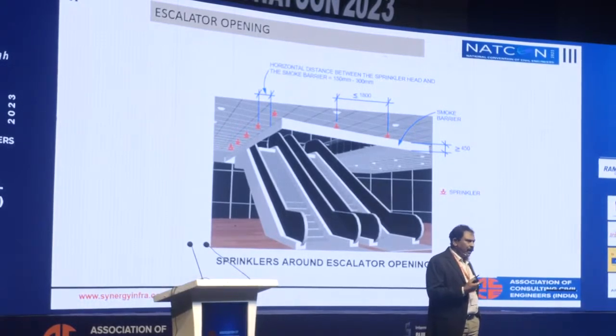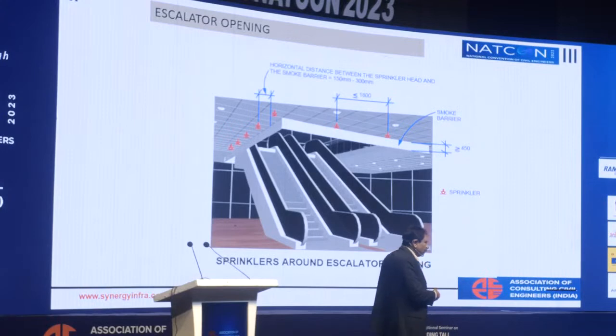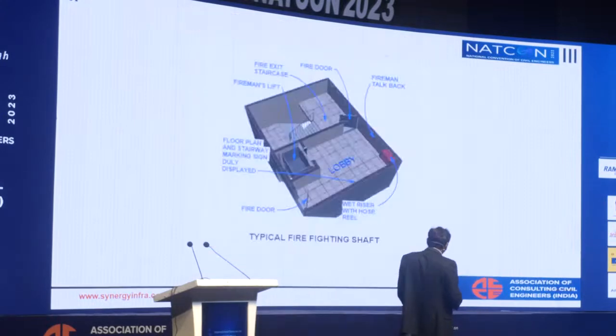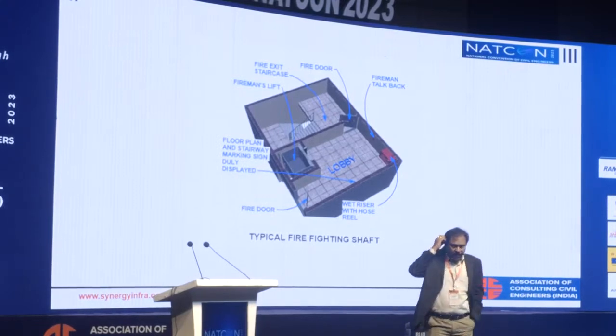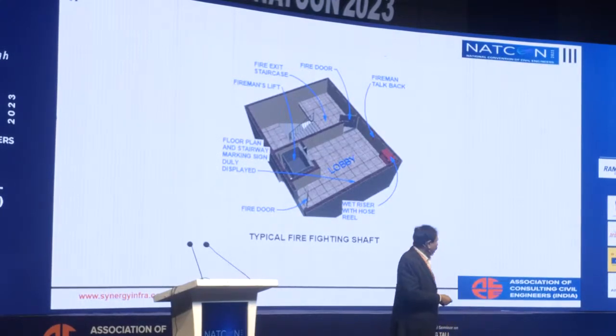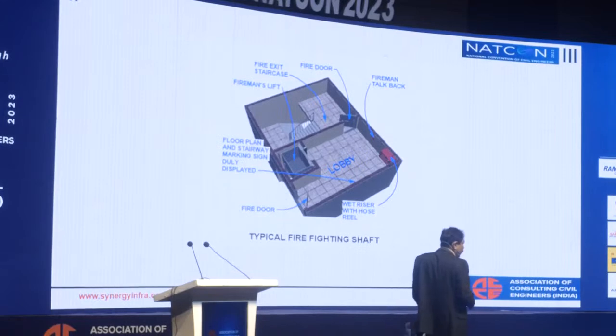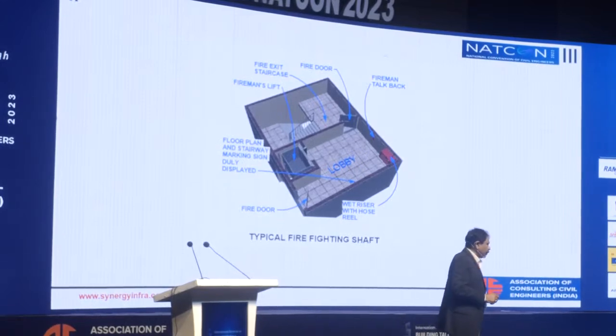So we need to have fire curtains all around those openings, or otherwise at least our code says have sprinklers at least. And this is the typical firefighting shaft. This is derived based on BS 9999. So where you have a lobby with a staircase and also a fire lift, which is used by the firefighters in case of evacuation requirements.